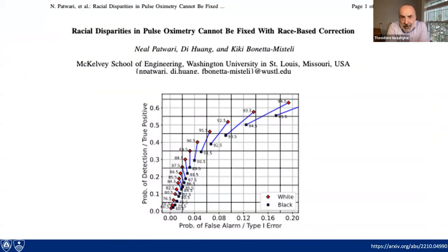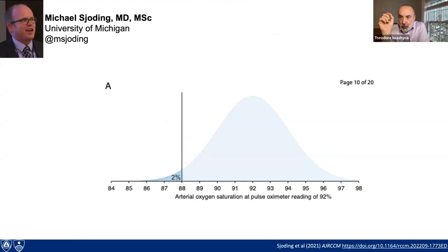The group out at WashU analyzed a bunch of other data, and this isn't quite an ROC curve—because it's engineers, and they think about ROC curves differently—but they basically say: you can't fix this. There's no cut point you can pick for your Black patients that just adjusts away this difference. The imprecision means the devices just measure less well, so you can't use a simple adjustment, like 88% for white folks, 92% for Black patients. The devices are just noisier, so you can't provide the same level of accuracy. Let me give you an intuition about why that is.